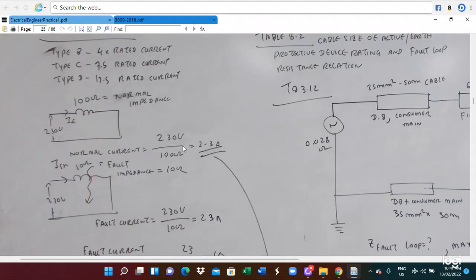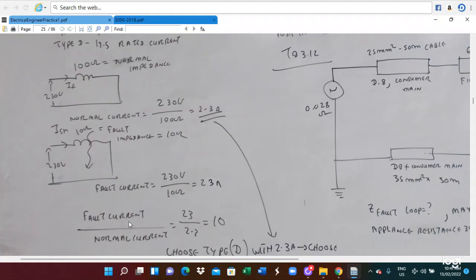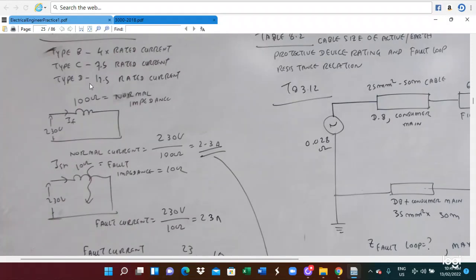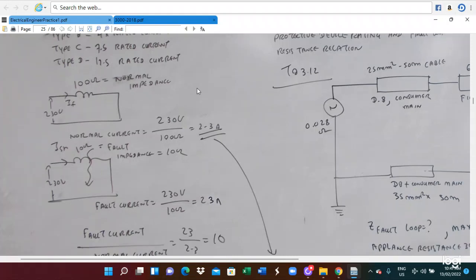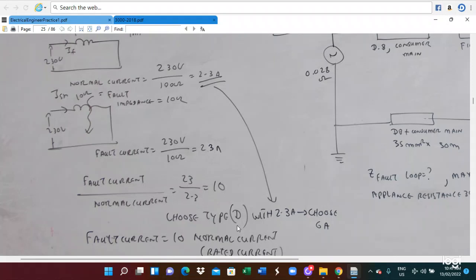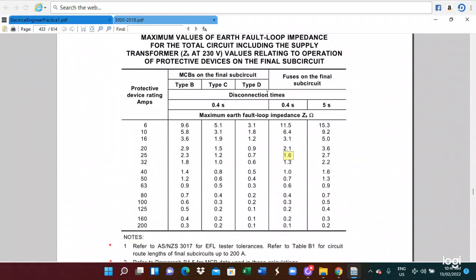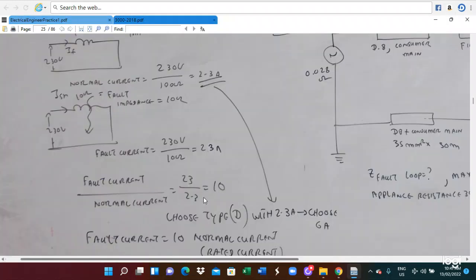Type B is only 4 times rated current, type C is 7.5 times. But here the fault current to normal current ratio is 10. So you cannot use type C, but you can utilize type D. Type D is up to 17.5 times. Therefore, you can utilize a type D circuit breaker, and also 2.3 ampere. So a type D circuit breaker, 2.3 ampere.